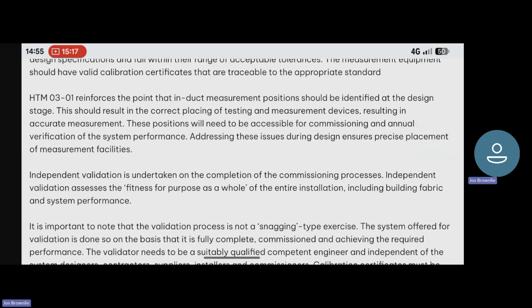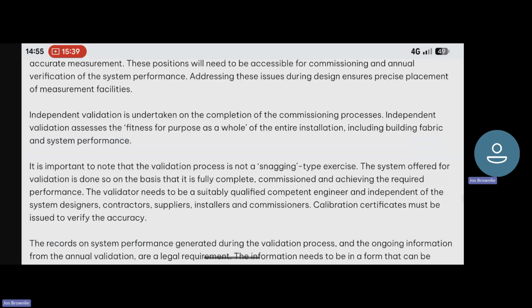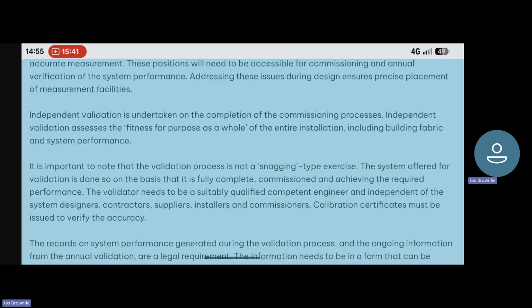HTM 03-01 reinforces the point that in-duct measurement positions should be identified at the design stage. This should result in the correct placing of testing and measurement devices, resulting in accurate measurement. These positions will need to be accessible for commissioning and annual verification of the system performance. Addressing these issues during design ensures precise placement of measurement facilities.